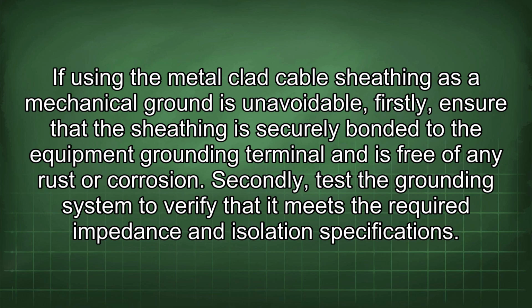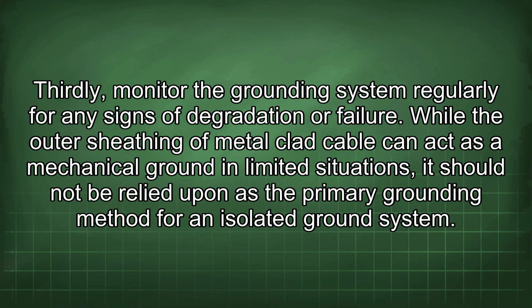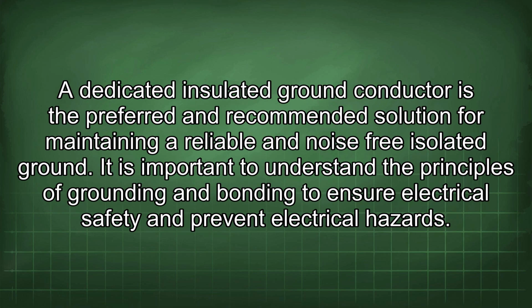Secondly, test the grounding system to verify that it meets the required impedance and isolation specifications. Thirdly, monitor the grounding system regularly for any signs of degradation or failure. While the outer sheathing of metal-clad cable can act as a mechanical ground in limited situations, it should not be relied upon as the primary grounding method for an isolated ground system. A dedicated insulated ground conductor is the preferred and recommended solution for maintaining a reliable and noise-free isolated ground.